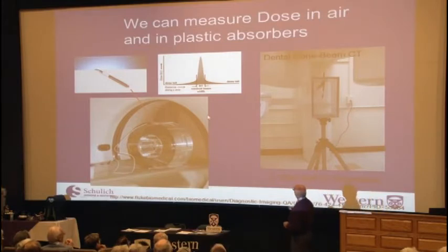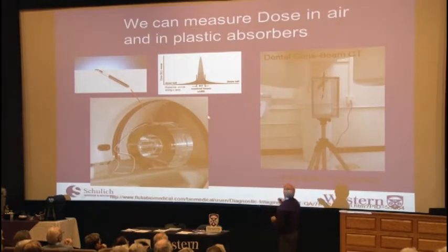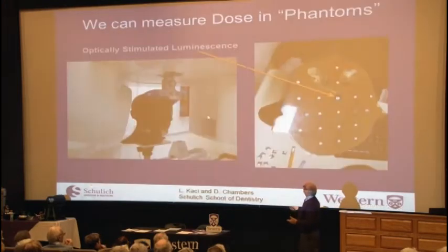And this is another one, harder to see, but we recently did some measurements on a cone beam CT scanner used in dentistry. It's a little hard to see, but one end of this has an X-ray tube, and the other end has a detector, and it takes images by scanning your head completely, similar to panoramic views you get at the dentist. And that's measured as well with the chamber that we put into the beam. That was done fairly recently, less than 6 months ago, calibrating that machine. So we can measure it.